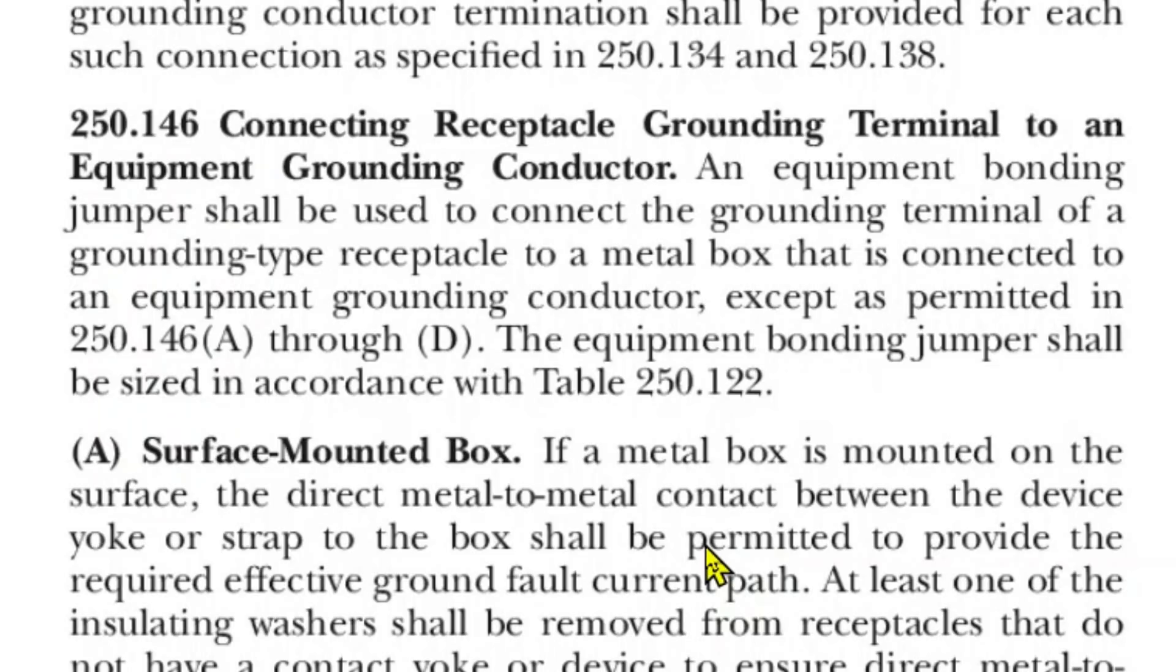Here we are at the 2020 NEC Article 250.146 Connecting Receptacle Grounding Terminal to an Equipment Grounding Conductor. An equipment bonding jumper shall be used to connect the grounding terminal of a grounding type receptacle to a metal box that is connected to an equipment grounding conductor, except as permitted in Article 250.146A through D. The equipment bonding jumper shall be sized in accordance with Table 250.122.